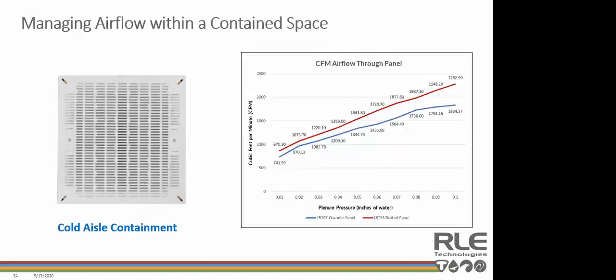So I'm going to hand it back off to James, and he's going to talk to us a little bit about managing airflow in a contained space. Right. Once an aisle is contained, it's important to know how to calculate how much cold air is required to cool that space. Ideally, enough air will be supplied to match or slightly exceed the IT load in that aisle.